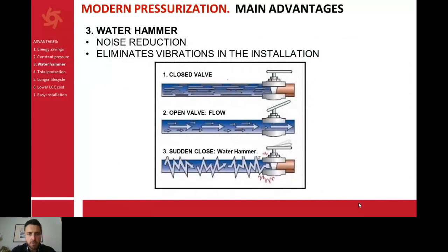Water hammer. You know this aspect: when we have a closed valve, we open the valve because water is needed, there is a flow, and when we have a sudden close in the old systems, we had the so-called water hammer. This is very dangerous because it can seriously damage the installations that we have. So in order to reduce or eliminate the vibrations on the installation, we have this modern booster set. As the speed of the pump goes in function of the demand, when you have a sudden close, it does not have any type of problems, because the pump will notice, and the transducer or the pressure sensor will tell the pump that it has to stop, and we won't have this water hammer.